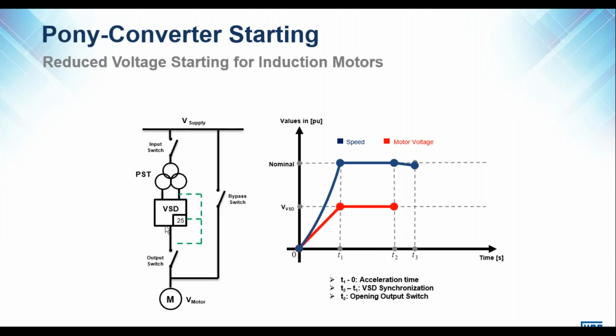In this case, I cannot synchronize and close both switches simultaneously because of the difference in the voltage output of the VSD and the supply voltage. So I have a momentary period where the VSD output switch is open. In that time, the motor voltage starts to drop. I then have a small window in which to apply my synchronism and close my bypass switch.